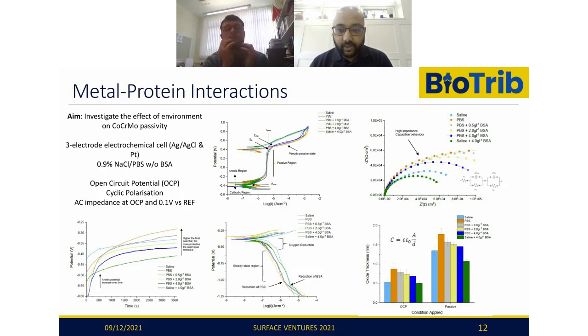It's interesting. Next question. Your pin on plate contact pressure is about two orders of magnitude higher than in vivo pressures. Is your method justified? Yeah. Another good question. I think the answer is, what's an in vivo contact pressure? For hard on hard joints we typically talk about tens, twenties of megapascals under standard joint loading conditions. As soon as you start moving to more adverse conditions, those contact pressures will go up. But it also depends on the geometry as well. You can achieve contact pressures in the area of gigapascals depending on how your components are orientated. So, yeah, it's a good question.